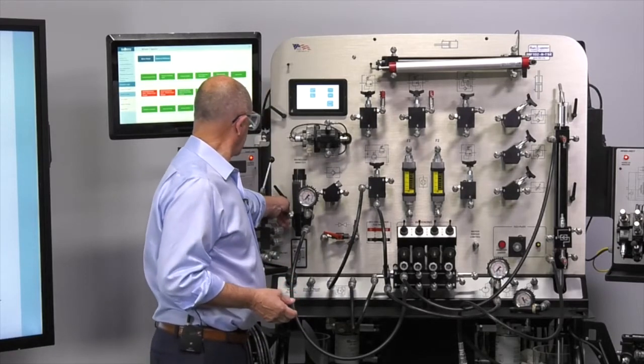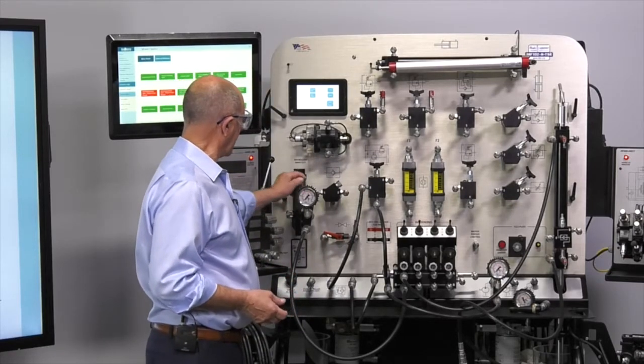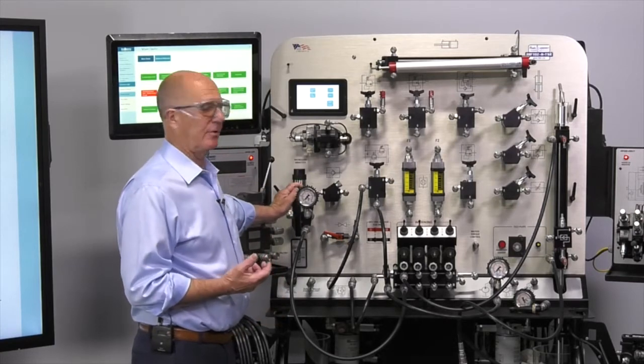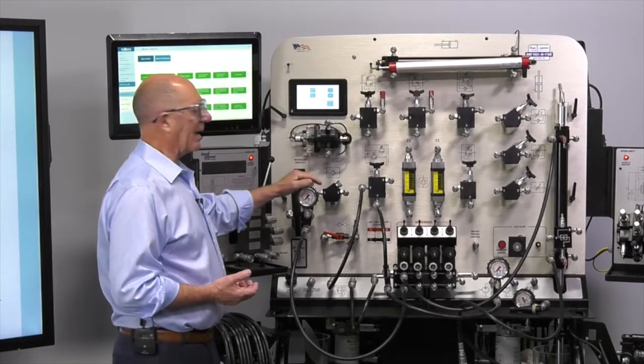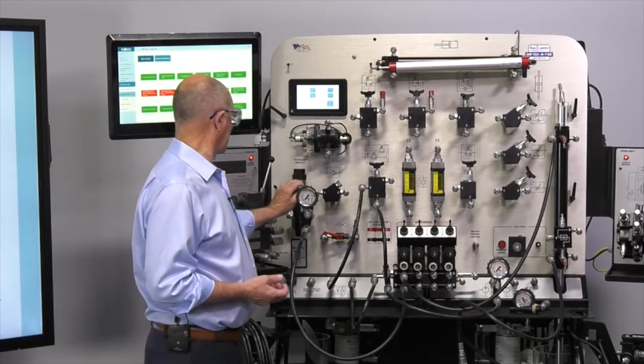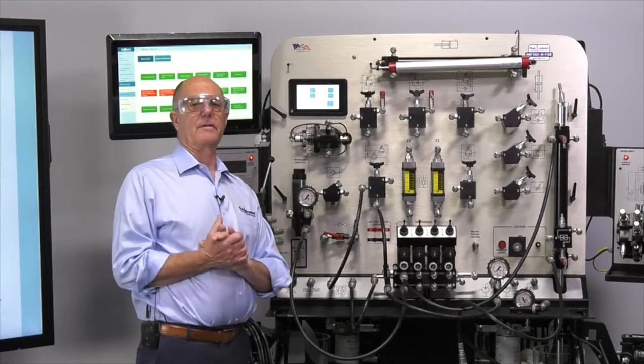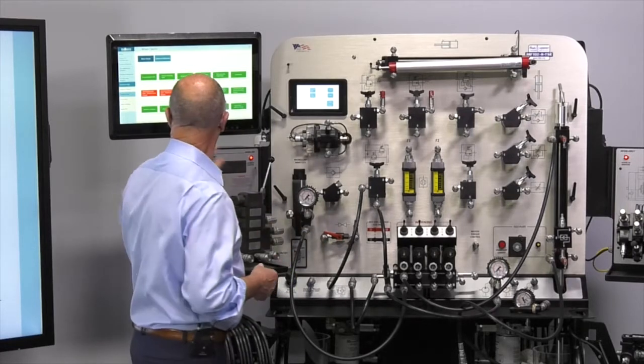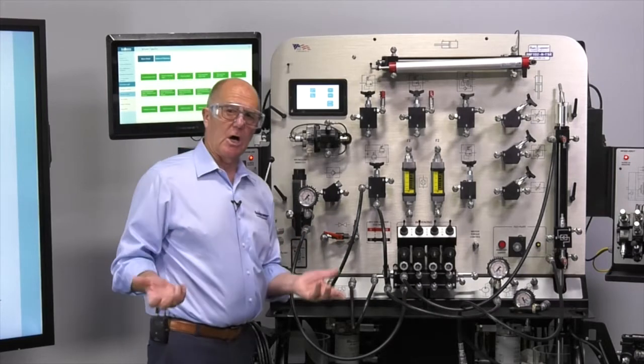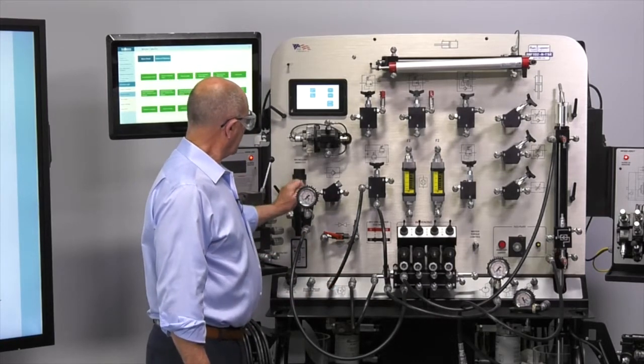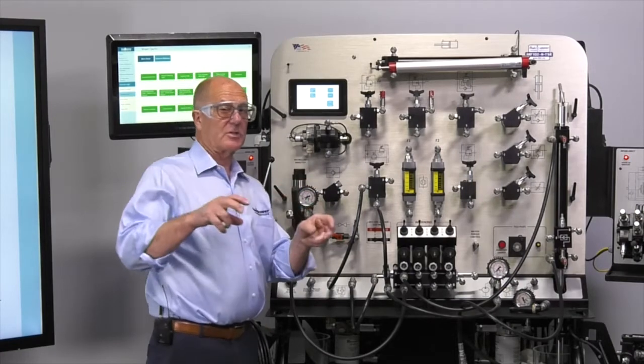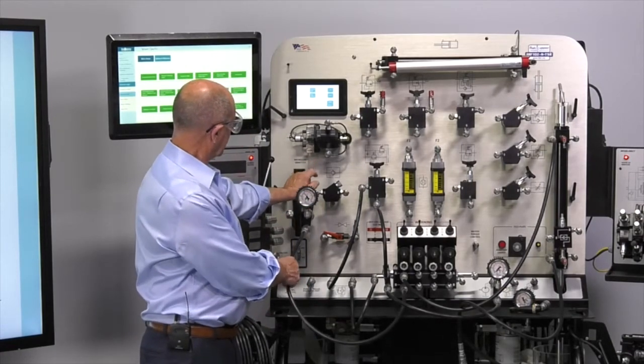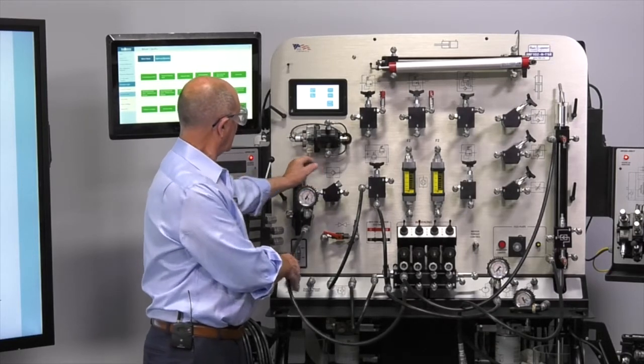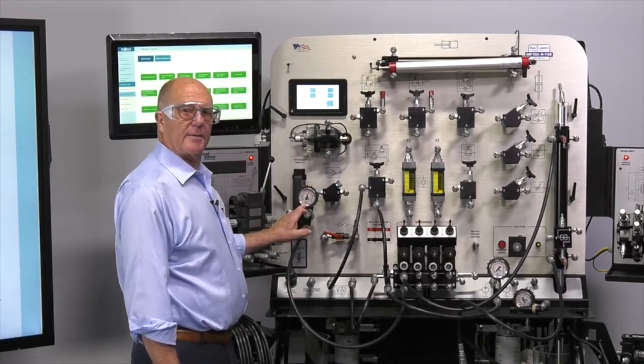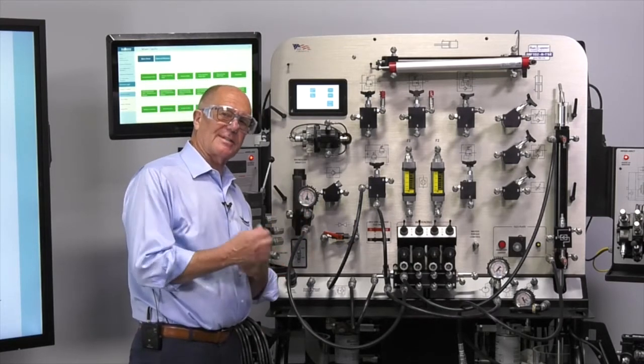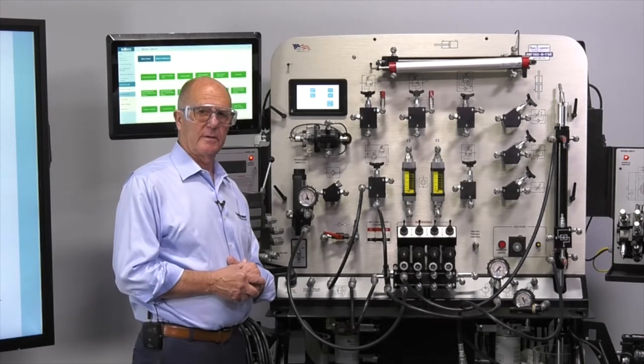Now I'm going to close the valve on the Microleak tester, and I'm going to pressure in, or at least attempt to. Notice that there is no gain on this pressure gauge, nothing whatsoever. Now you might be saying, well, what does it look like when the valve is good? Well, let me show you. Let's take the fault out. The fault's gone now, and let's do it again. The minute you take the fault out, when the valve is not leaking, you'll immediately build pressure. And since the valve's a leaker by design, you'll notice that it'll slowly bleed down. The mere fact that I got resistance tells me the valve is in perfect working condition.